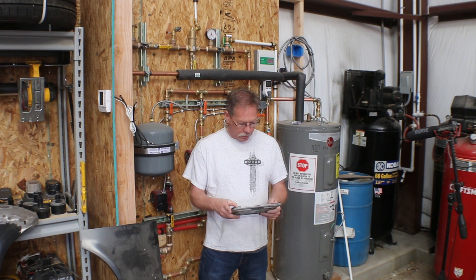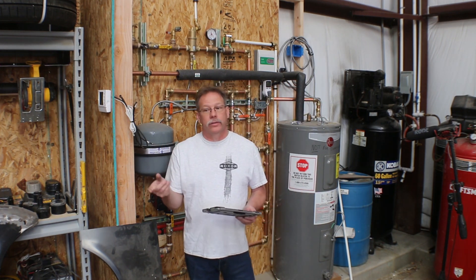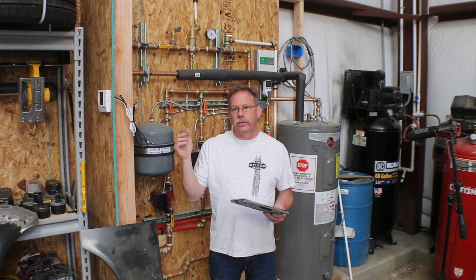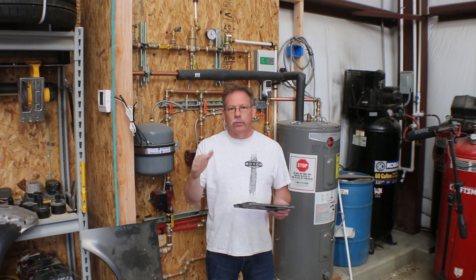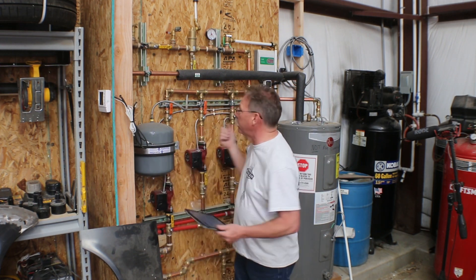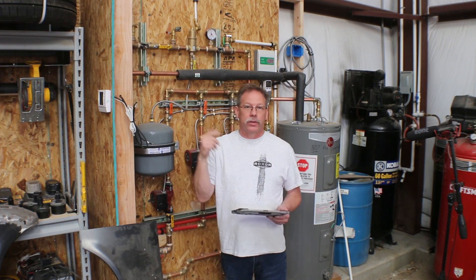Let me go through some questions. Are the floors insulated? Yes. My slab is roughly seven inches thick on average and has all the tubing tied to remesh wire, with insulation underneath — I believe it's R7 or R8. It's fairly thin but fairly expensive insulation to get that quality at that thickness. People also said a mixing valve would probably help, and I think that's probably true, especially as I work on the system going forward.